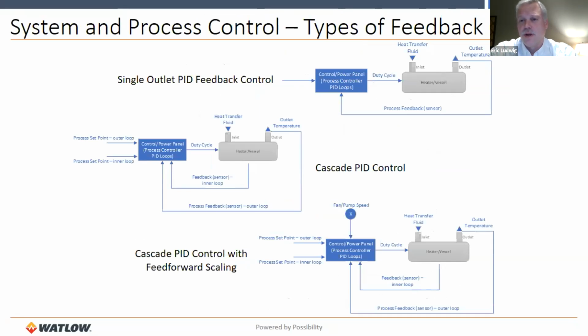And so those are some of the trade-offs that we would have to make when considering it. I'm going to talk a little bit about the process control types. We talked earlier about the PID, the integral. These are just block diagrams of some of the different types of controls that may be used in the process controller itself. So you see the gray box represents the heater or the vessel. It's got an inlet where the fluid comes in and an outlet where the heated fluid comes out. You're typically measuring the outlet temperature of that fluid to make sure it's well within the process parameters that we need. A typical PID loop would take that outlet temperature, compare it to a set point value, and then just turn on and off the heaters to ensure that that outlet temperature is being met. And that's how a traditional feedback control loop would work.